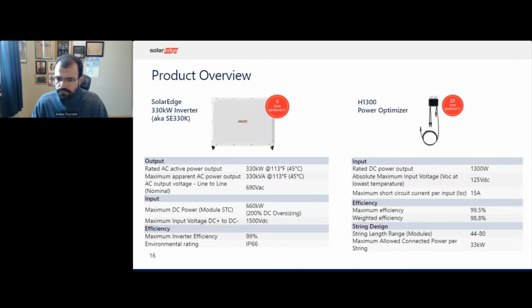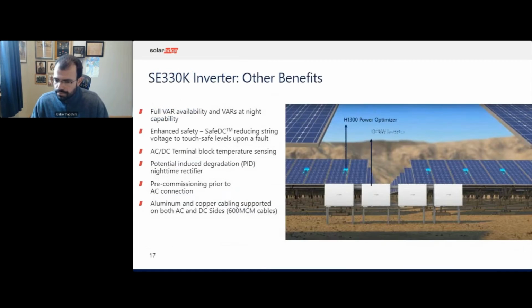Okay. So other characteristics that I believe are noteworthy to talk about on this solution. VAR support. This inverter can push all the 330 kW in the form of 330 kVAR, so it can go all the way to power factor 0 if need be, for grid support. And as Varsha said, because of the optimizers, the system includes DC optimizers, and upon any fault, upon any issues, the DC optimizers will lower voltage levels at the string level to touch safe levels within minutes. Now, question, does it have rapid shutdown? No, it does not have rapid shutdown. However, it has a shutdown piece.